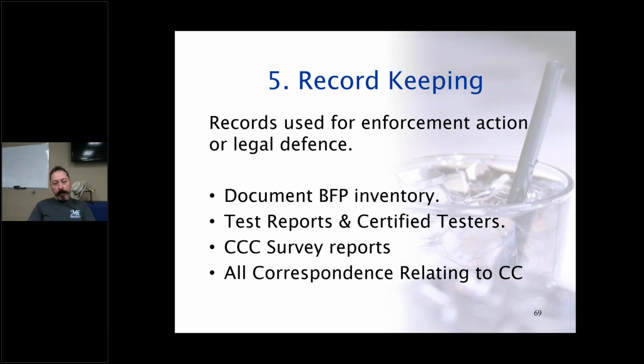What would I keep? Well, I would keep documentation of all my backflow preventers, the inventory of my backflow preventers, as far as the testable ones anyway. We want to make sure our pressure vacuum breakers, our RPs, and our double check valve assemblies are inventoried. I know where they are, the model, makes and serial numbers, and what they're isolating. I would have test reports on those, done by certified testers.